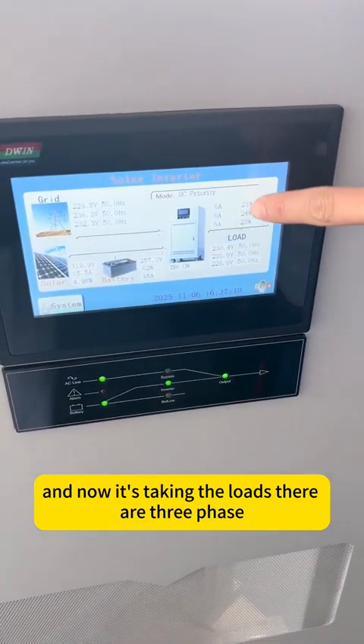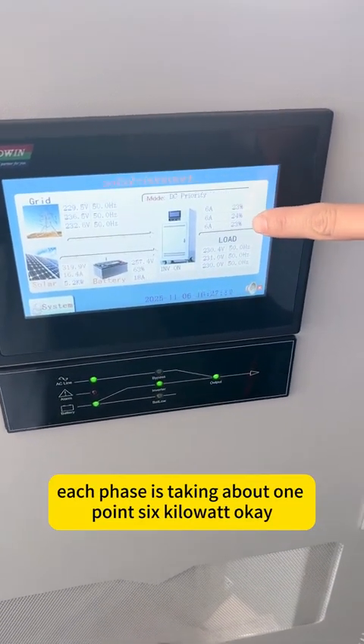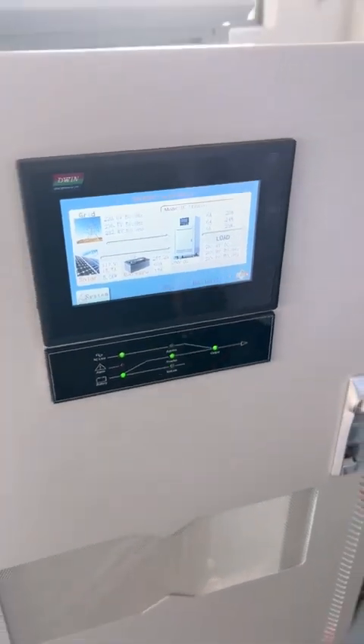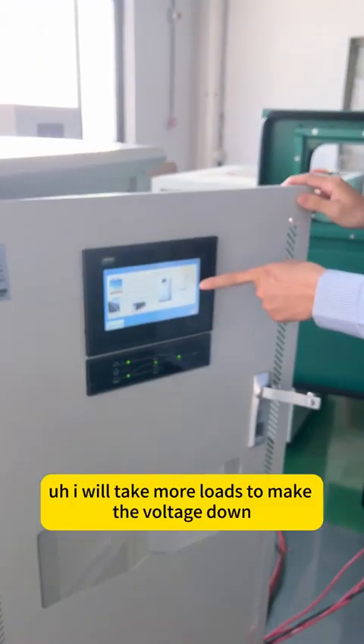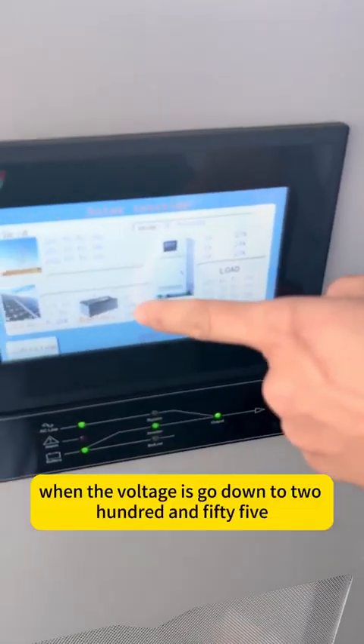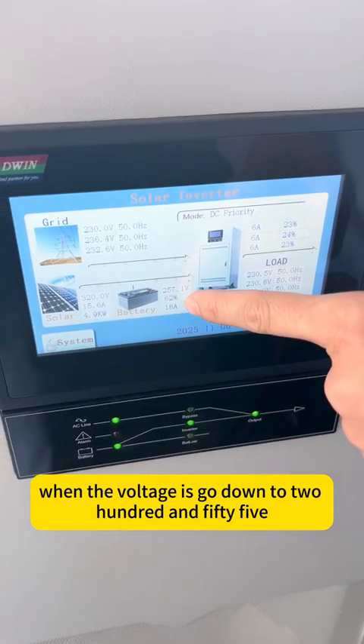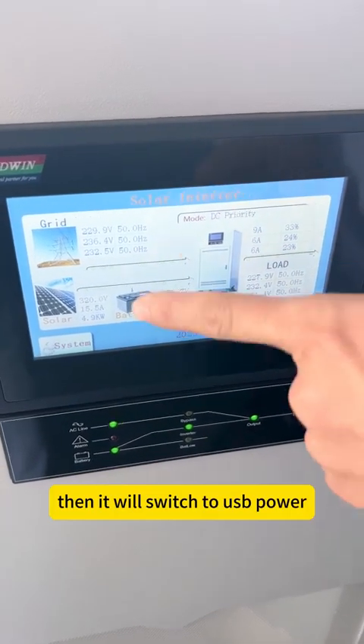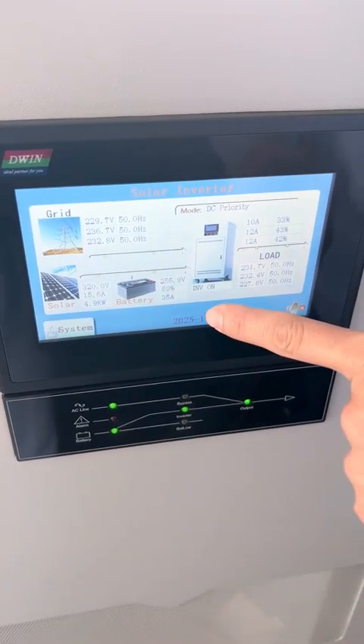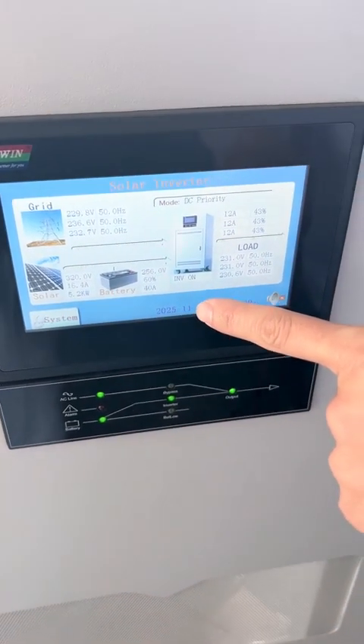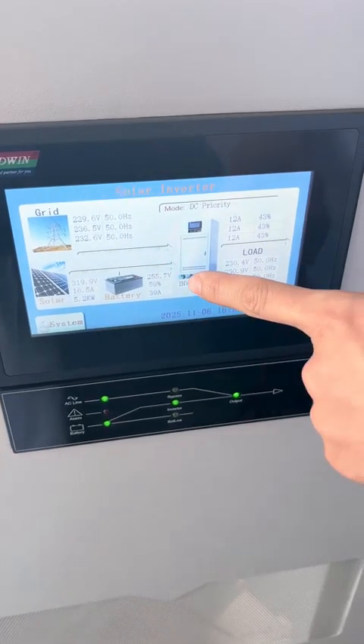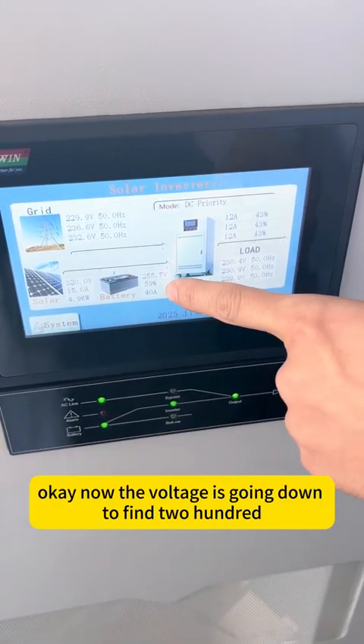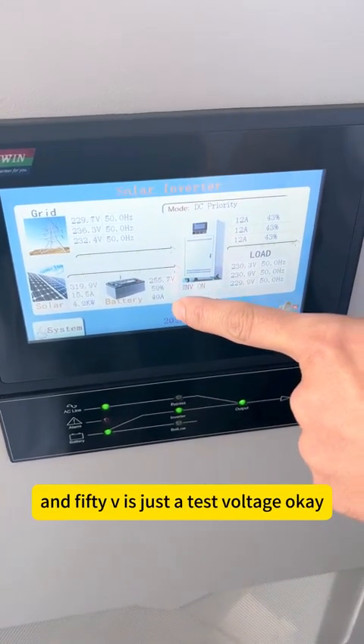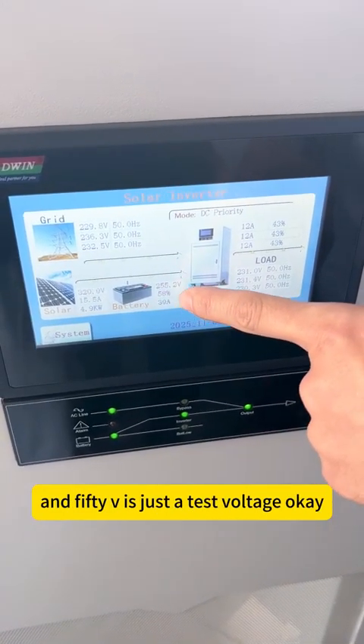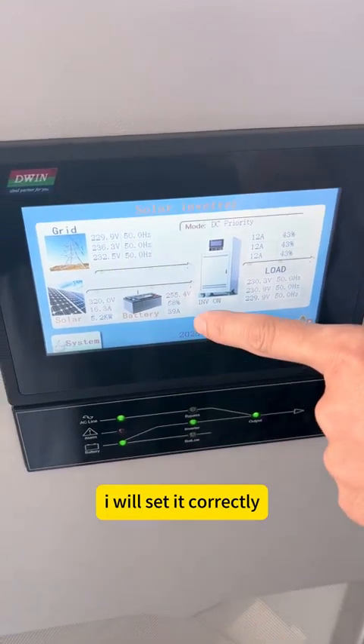See, three phase. Each phase is taking about 1.6 kilowatts. I will take more loads to make the voltage go down. When the voltage goes down to 255, it will switch to use grid power. Now the voltage is going down. 255 is just a test voltage. After the test, I will set it correctly.